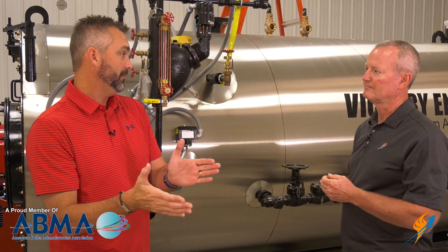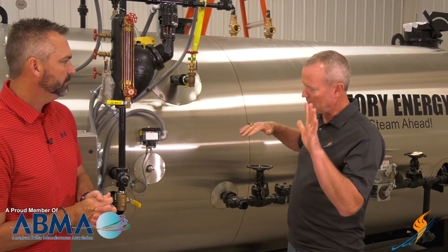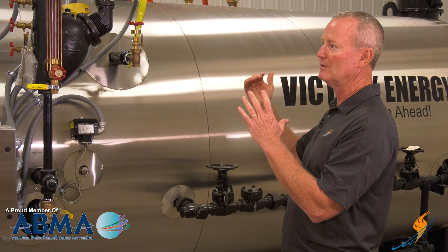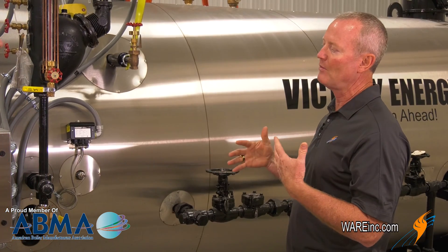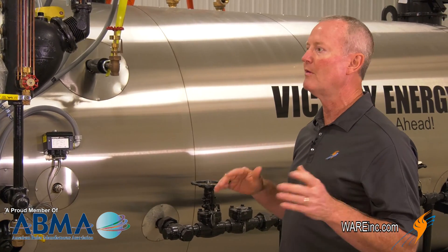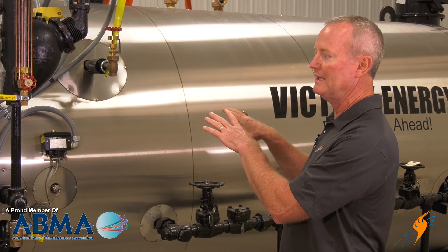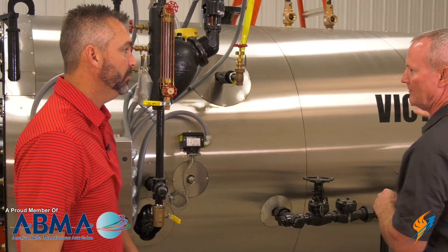Lots of damage comes from low water, including some catastrophic stuff. If it gets low enough and exposes the Morison tube — which is the main fire tube — then that fire coming through that tube will overheat that steel, and the steel will droop and fail. Most of the time, a catastrophic failure happens when someone turns the water on and you've got that thing that's super superheated, and you inject water into it. That water turns to steam immediately, and boom, you just have an explosion.